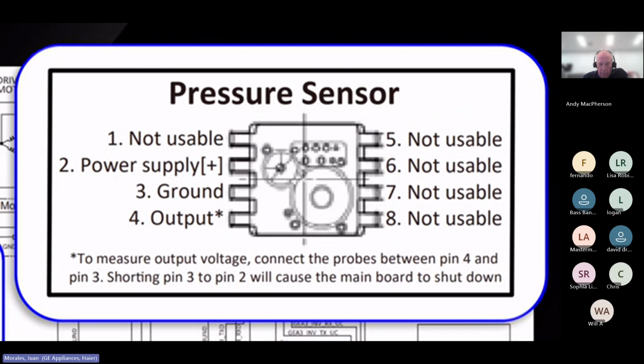This allows you to know what voltage is coming out of the pressure sensor. Based on a table in the mini manual, you'll know if there's water in the tub or not, or if there's a problem with the pressure sensor, in which case you'd need to replace the main board. But it's also giving you important safety information, saying shorting pins 3 to 2 will cause the main board to shut down. I don't know if this means the main board may shut down temporarily for a couple minutes, for 10 minutes, or if it's going to get fried permanently. Either way, I do not want to find out the hard way. So I am not going to short out those two pins now that I know this.